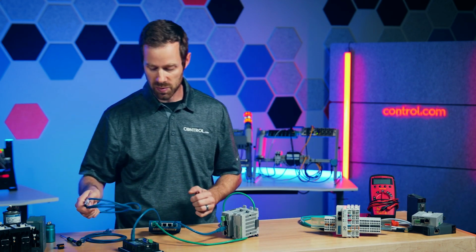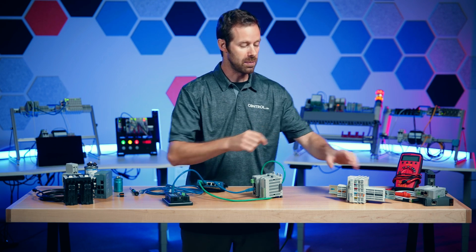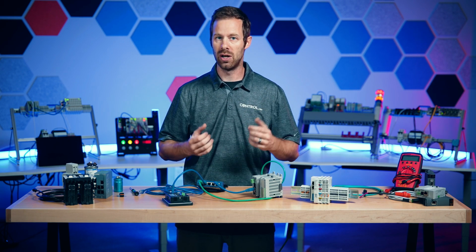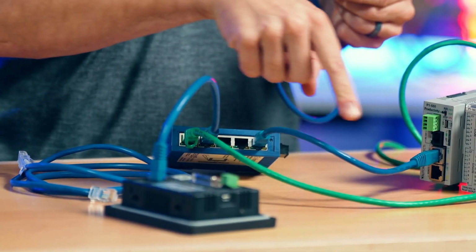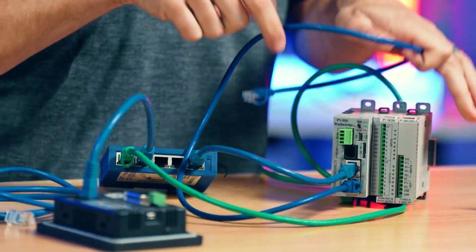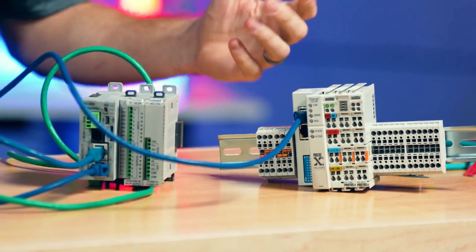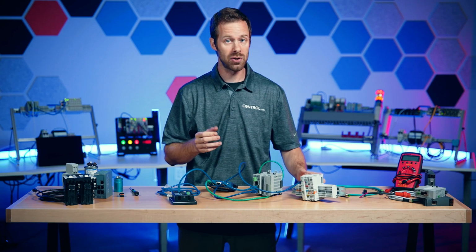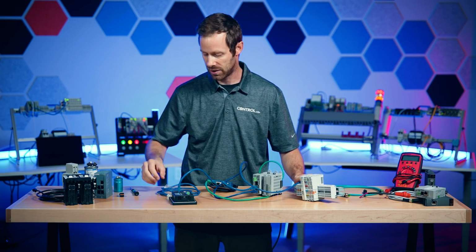The other type of topology is what we call ring. Now, ring topology is very important in the control and the remote I/O system, because if anything is to lose communication, we certainly hope it's not our controller. So as before, we have one connection from the switch to our controller, and then we have a connection from the controller to the remote I/O devices. Very often these remote I/O devices, just like this one, will have two Ethernet ports. You can buy controllers with one Ethernet port or two, and this is one of the benefits of two connections.